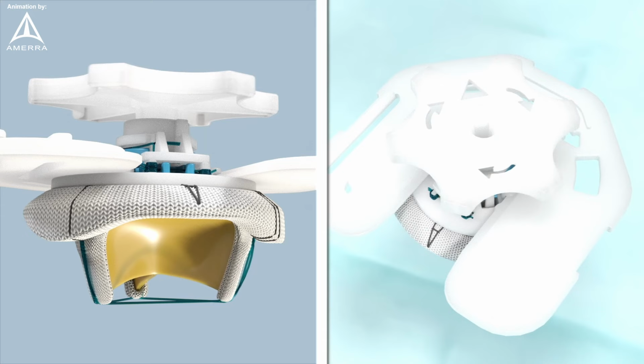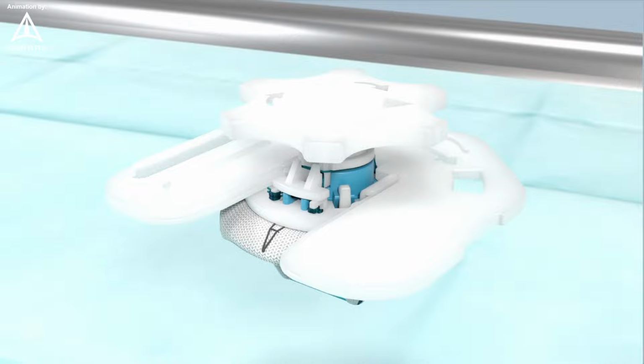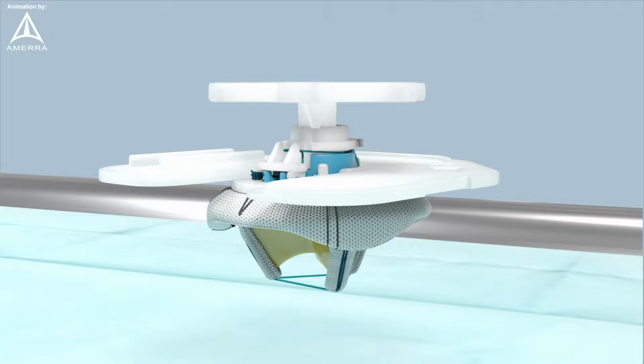Remove the valve from the inner tray by grabbing the dial. Do not try to insert the handle into the dial at this point. While holding the retainer, turn the dial clockwise to fold the valve commissure posts. Turn the dial until the triangle on the dial is at the landing zone on the retainer and a hard stop is felt. It's normal to hear a clicking noise. After the stent posts are folded, remove the dial from the holder system by pulling up on the dial.